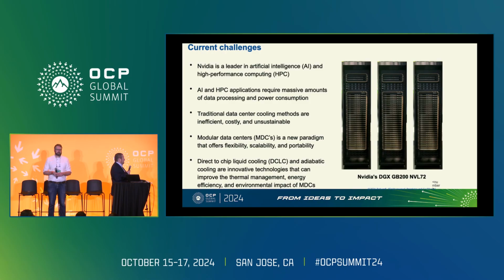So the challenges of the NVIDIAs represent a whole paradigm shift: direct liquid cooling, getting enough chiller systems, getting enough generators out there to take care of that. You're going to have UPS for the liquid cooling chillers. All that is a paradigm shift, and the current supply chain isn't really ramped up to handle this type of demand in this short order.